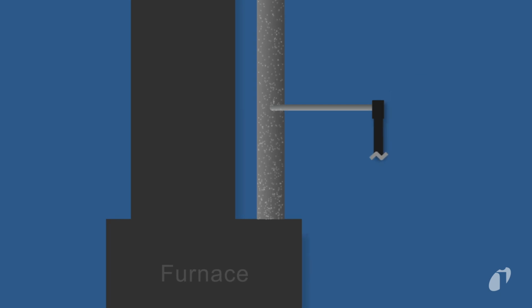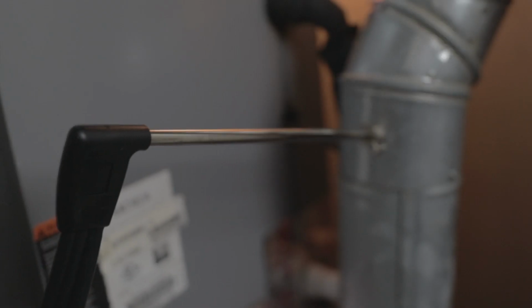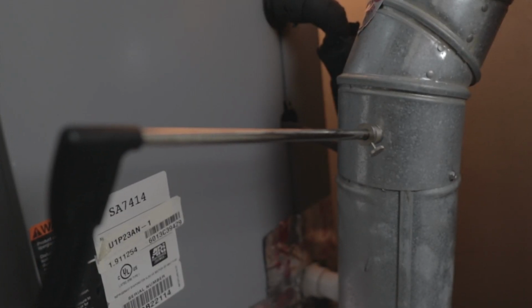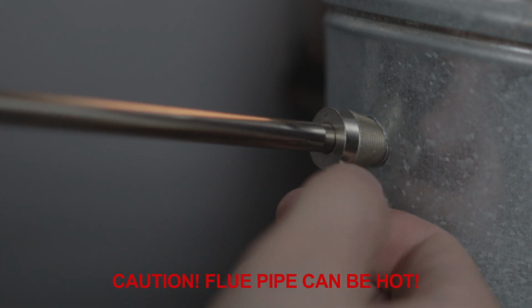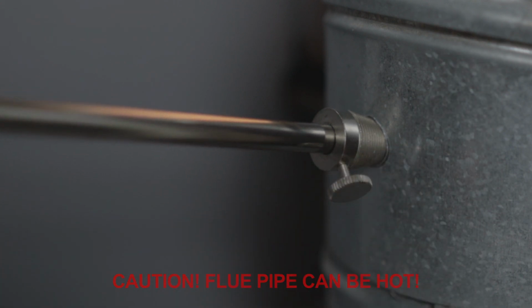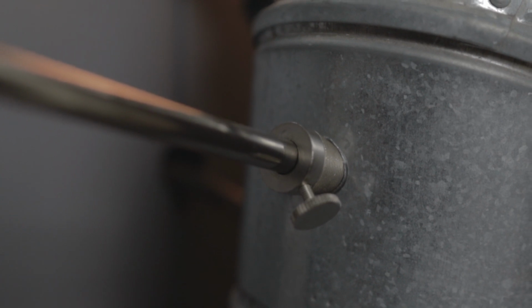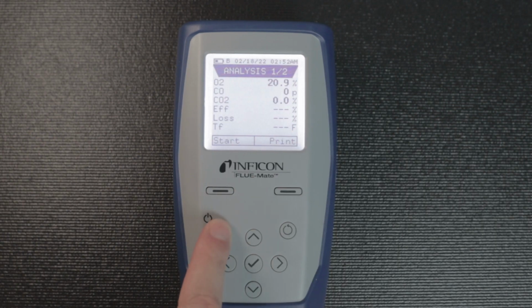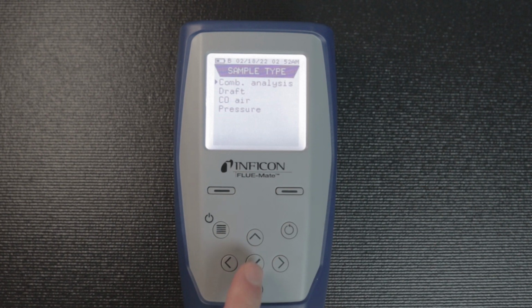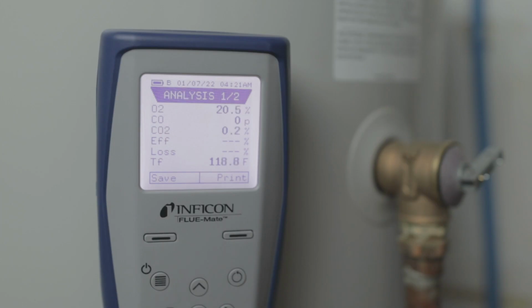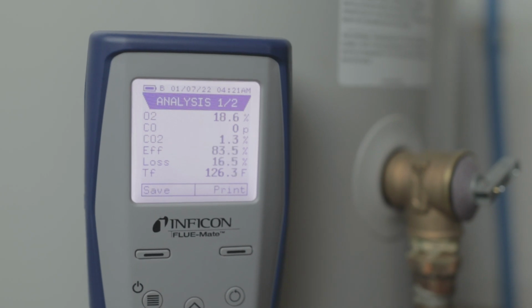Insert the gas sampling probe into the test port. The tip of the sampling probe should be in the center of the pipe. Loosen the set screw to adjust the positioning cone. Screw in the positioning cone when the probe tip is in the correct position, and then tighten the set screw. There should not be any noticeable gaps. Select the analysis mode and fuel type before pressing the start button to begin the analysis. On the screen, you'll see readings like oxygen, carbon monoxide, carbon dioxide, system efficiency, losses, and flue gas temperature.